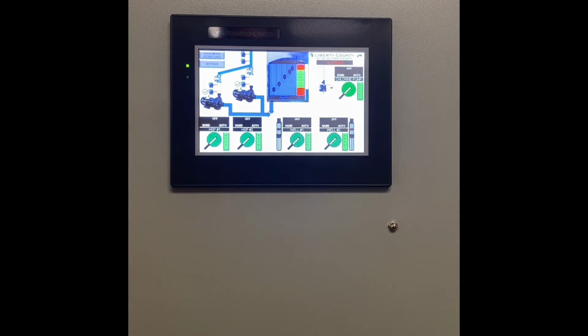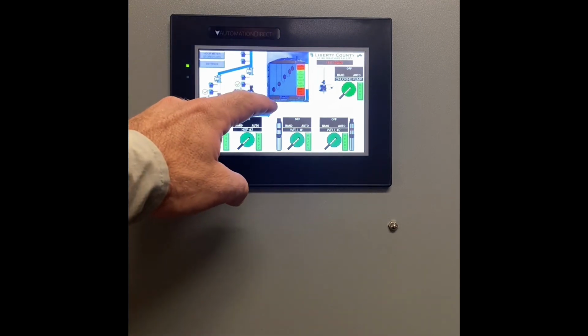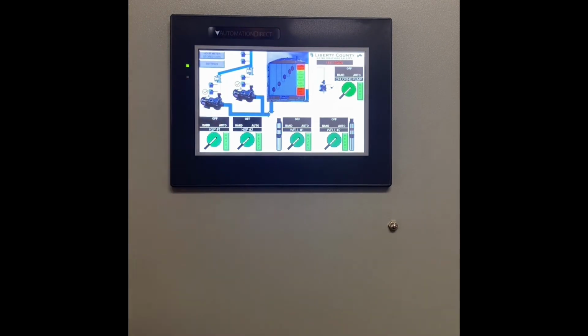Now, right now, for testing, I am simulating that the normally closed float is in good shape on the high service pump cutout. And you'll notice that the piping leaving the bottom of the tank and coming over to the 2 high service pumps is blue. If that switch drops down, then that piping internal will turn red to alert the operator that we have an issue.